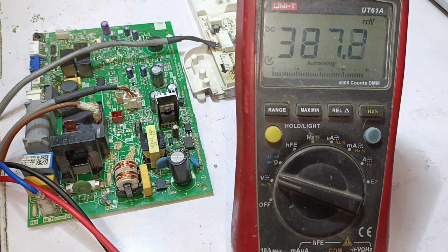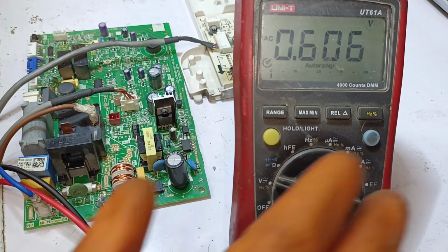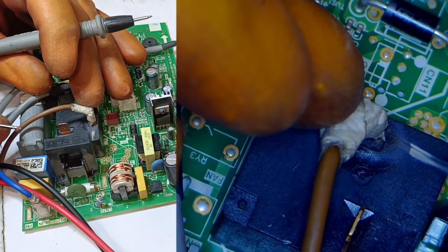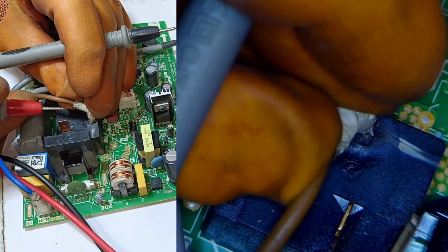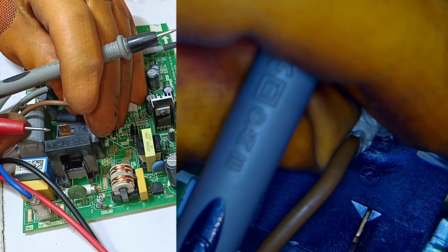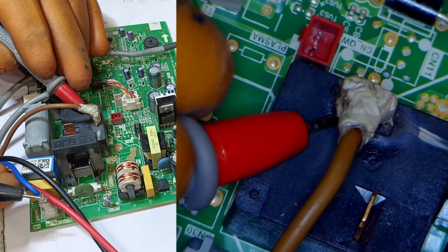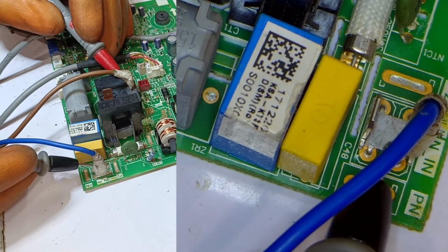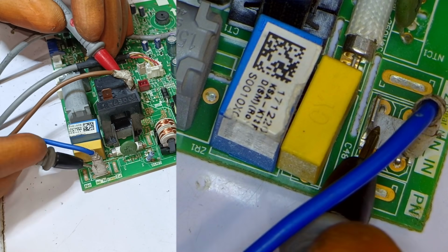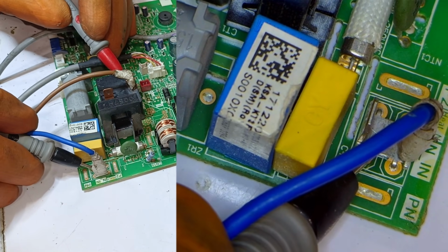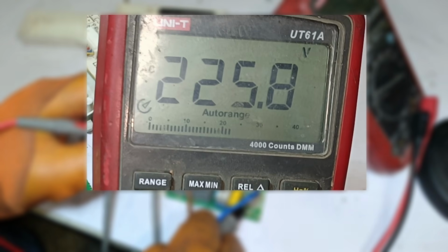To check the main power supply, I set the multimeter to AC voltages. This is the main common terminal where the line wire is installed. I place the red probe on the relay and the other probe on the neutral terminal of the circuit board. After placing it there, I can see 225 AC volts are coming through.